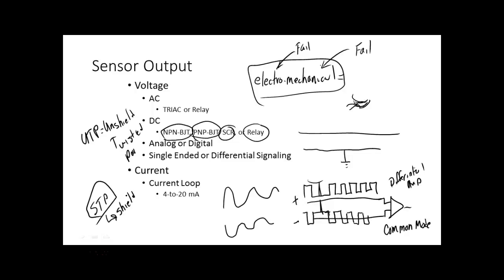So if you ever run into a twisted pair cable, don't untwist it. Because when you untwist it, you change what we call the characteristic impedance of the cable, which means that's going to cause all types of problems. So you need to try to keep it in the twist as much as you possibly can. Don't twist it any more or any less, because how many turns you have per inch is part of what sets the impedance of the cable.